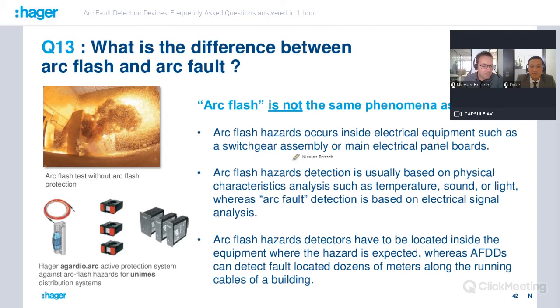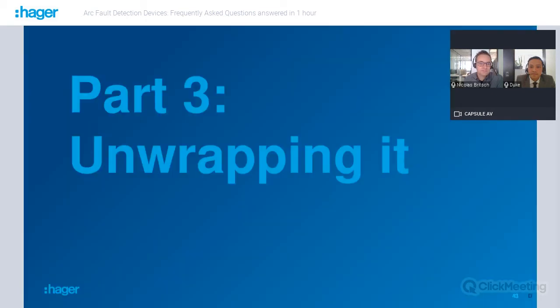And here on the left, you have an example of an arc flash test, without the arc flash protection, so you can see the kind of energy that you have in this kind of fault, which is much bigger than an arc fault. And here below, you have an example of the Hager offer, which is called Hager agardio.arc, which is an active protection system against arc flash hazards for unimes distribution systems. So this is not the same kind of fault. Arc flash is not the same as arc fault. Okay, it's clear. Thank you, Nicolas.